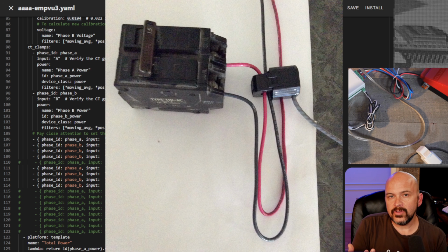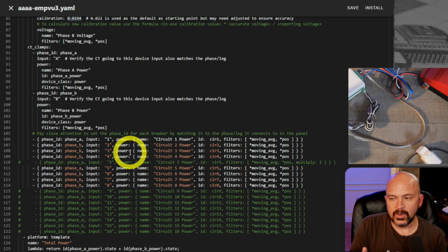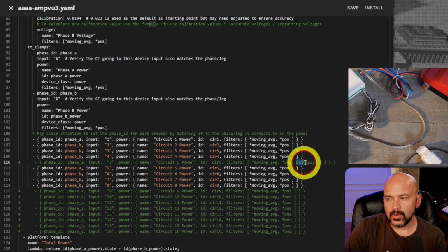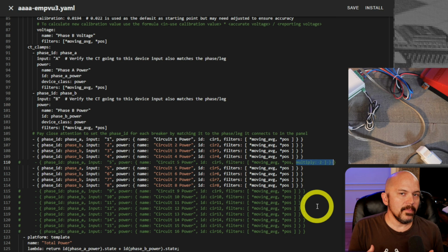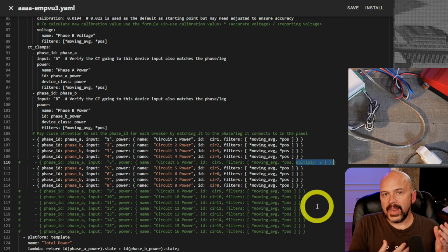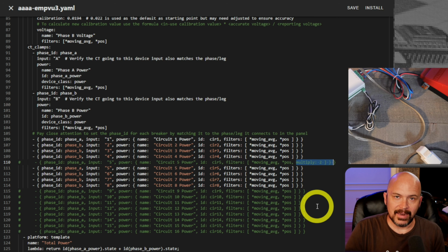Now, if you can't do that, you don't have the slack to do so, you can use the config here. You can see we have one commented out, it has a multiply. Now you may multiply the wrong leg, which is, say, the one that has the blower motor on it, and then you end up with too much watts or not enough watts, depending on which one you get, because it's an unbalanced load between the two hot legs. It's just kind of that thing you have to deal with.